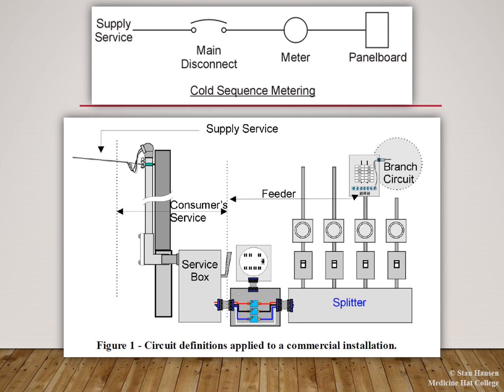So cold sequence metering takes everything through the service box first and then to the rest of the service equipment second. So we come to the service box and then to the meter and then to our panel board. This is the safest type of service because when I turn off the main service box, it makes everything else behind it dead.